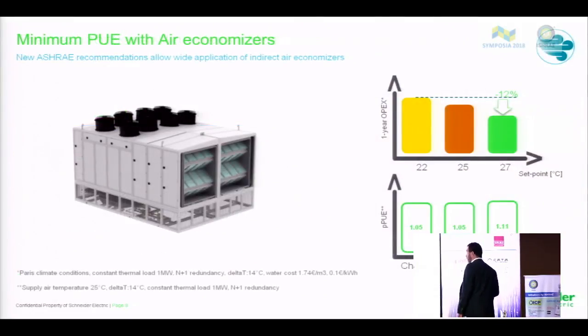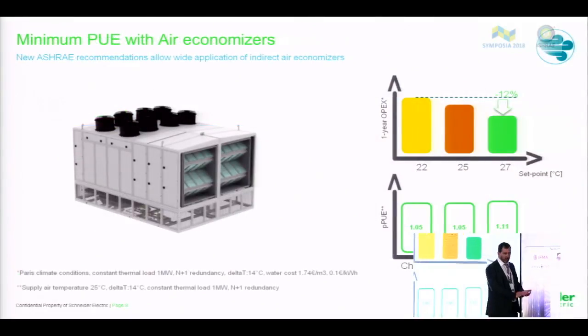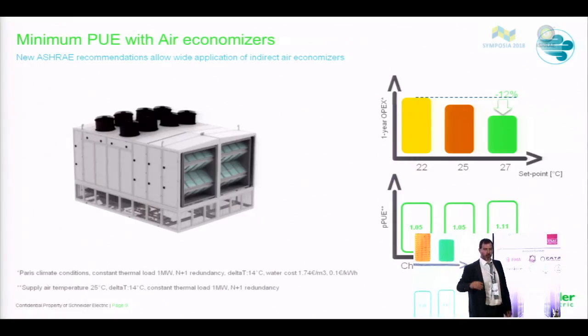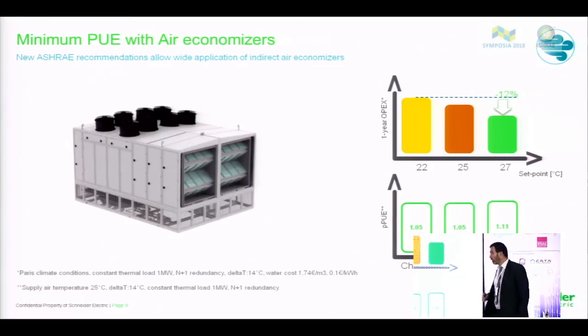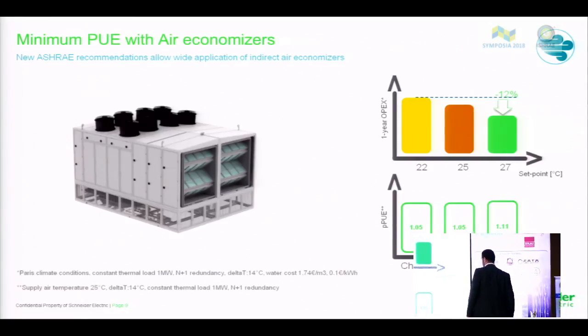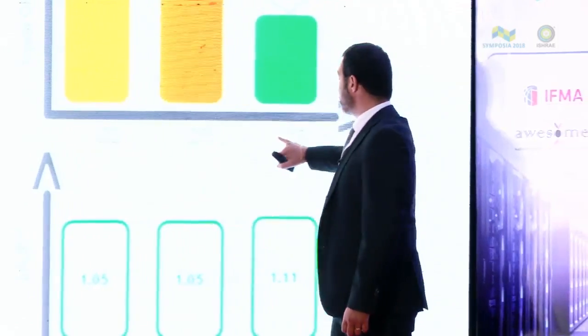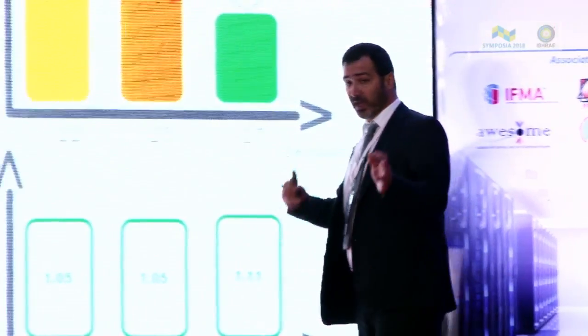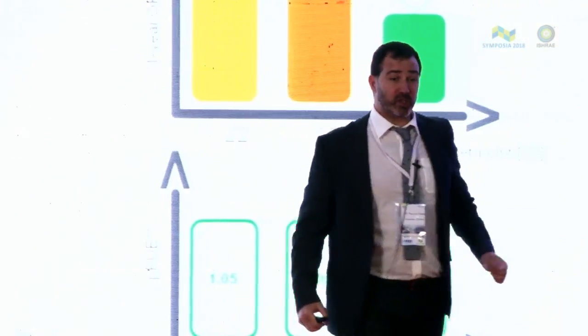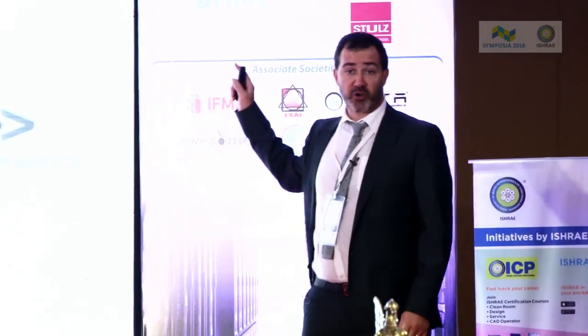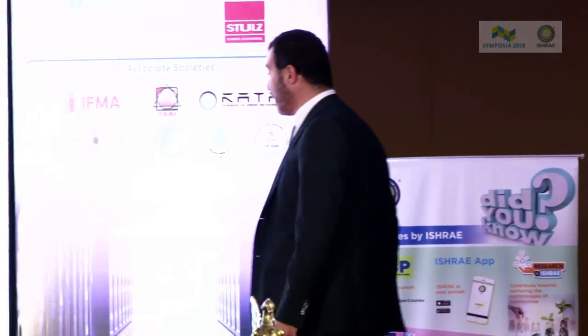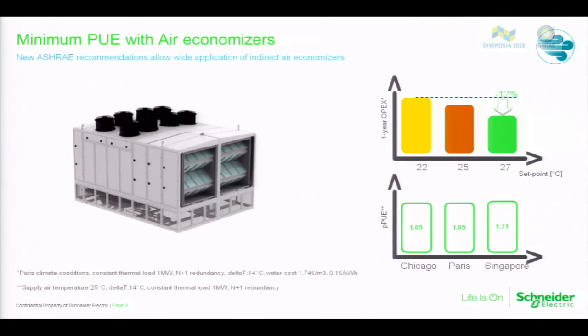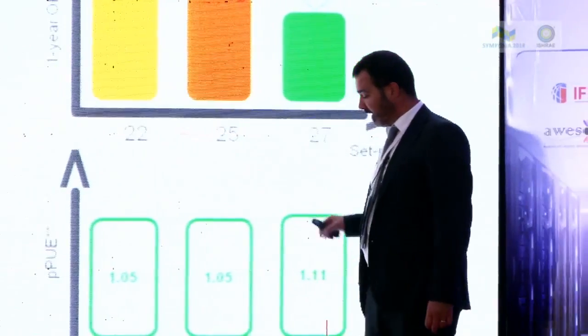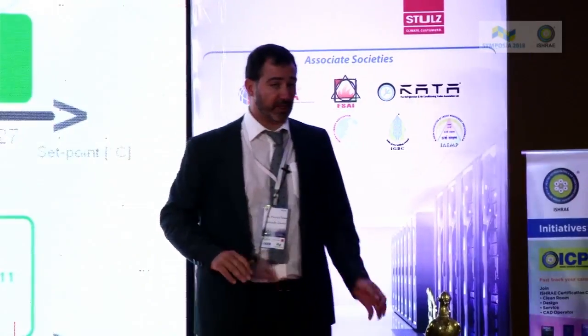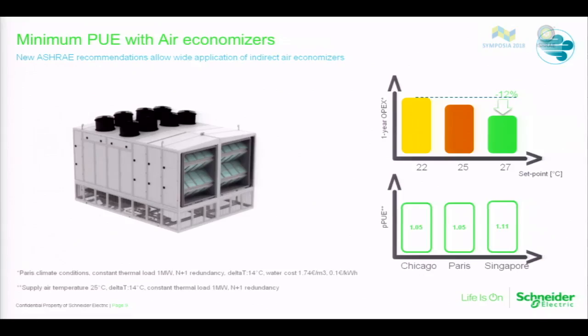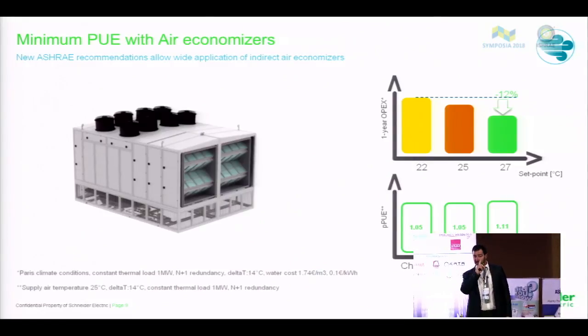which is applicable not only on chilled water systems. If we move on and jump on the other side of the design, the air economizer, the air handler, again the more we increase the set point, the more we are able to reduce the OpEx. If you design an air economizer at 22 discharge or at 27, there is a relevant difference in terms of power consumption. And the PUE, considering 25, is really low in a worldwide comparison. So definitely, the air economizers are based on the same concept, are based on an important point.